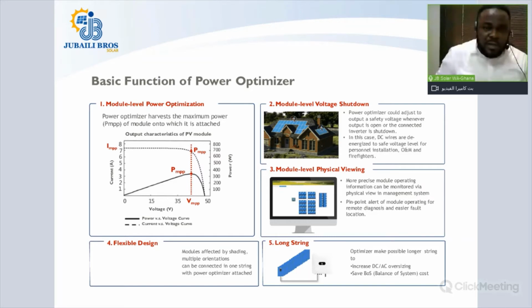The second function of the optimizer is to enable module level voltage shutdown. As soon as the PV side is de-energized, this optimizer shuts down to 0 volts to safely isolate the PV DC side. So if the circuit that leads to the PV inverter becomes open, or the inverter is shut down, immediately, rapidly, the optimizer shuts down the system to 0 volts. And this is very, very good for the DC side and also for firefighting and for other hazards that might occur on the PV DC side.